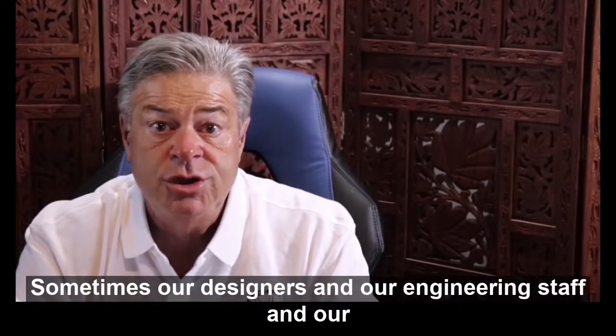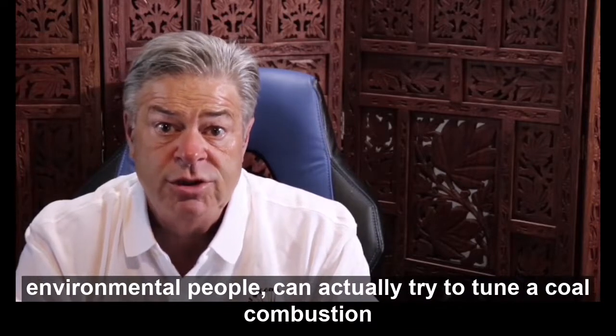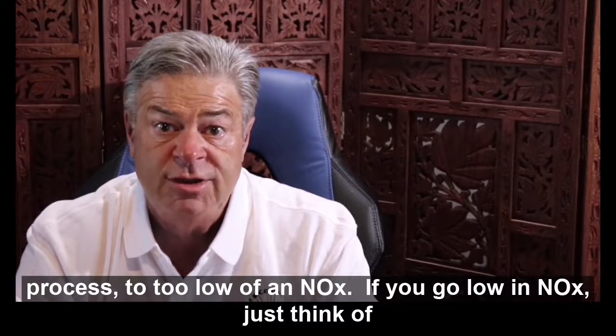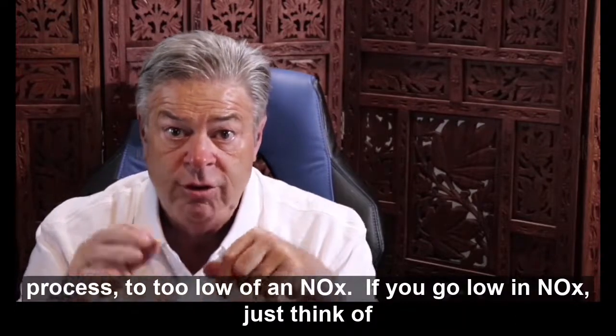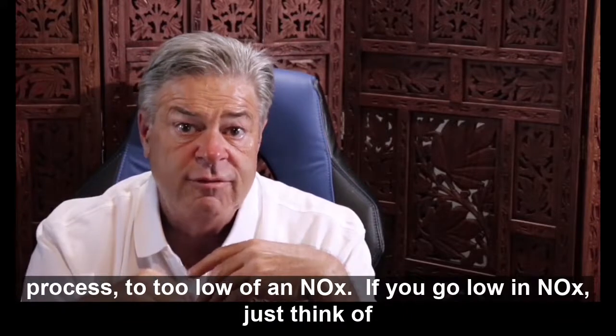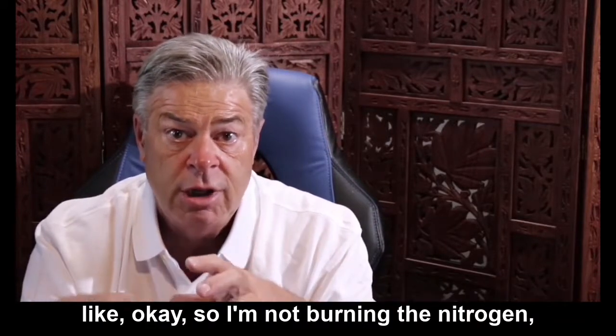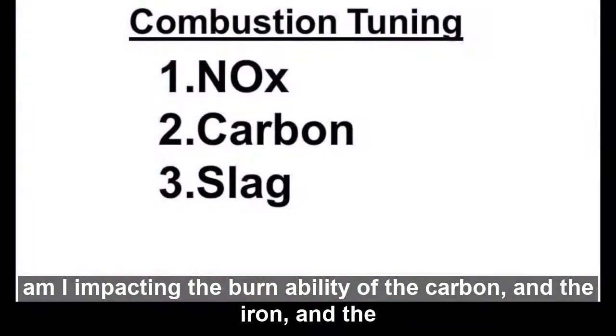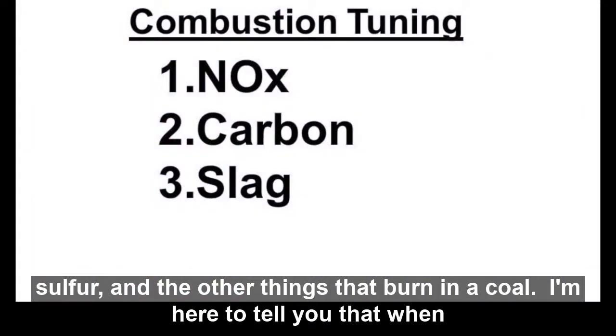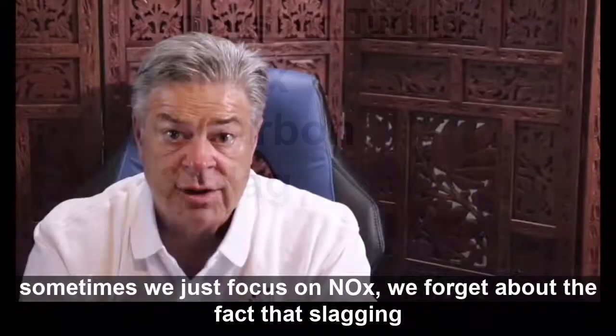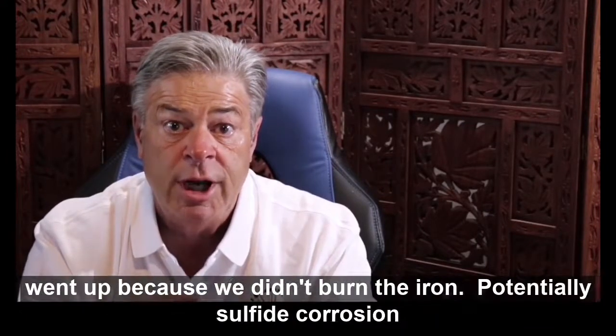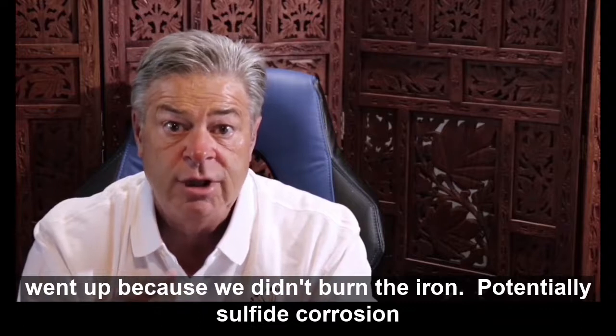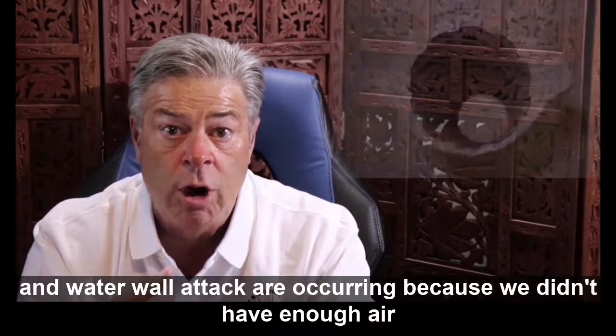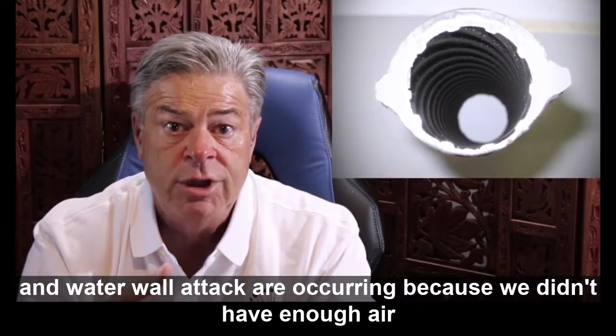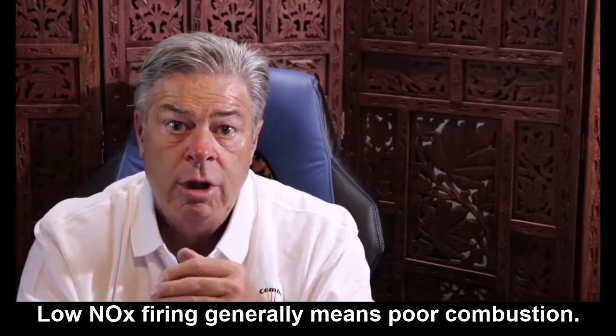Sometimes our designers and our engineering staff and our environmental people can actually try to tune a coal combustion process to too low of a NOx. If you go low in NOx, just think, okay, so I'm not burning the nitrogen. Am I impacting the burnability of the carbon and the iron and the sulfur and the other things that burn in a coal? I'm here to tell you that sometimes when we just focus on NOx, we forget about the fact that slagging went up because we didn't burn the iron. Potentially sulfide corrosion and water wall attack are occurring because we didn't have enough air in the furnace zone.